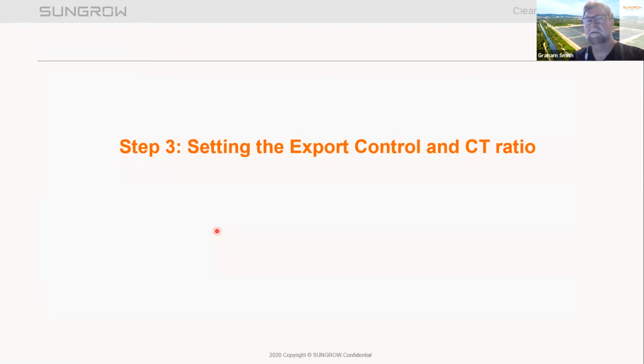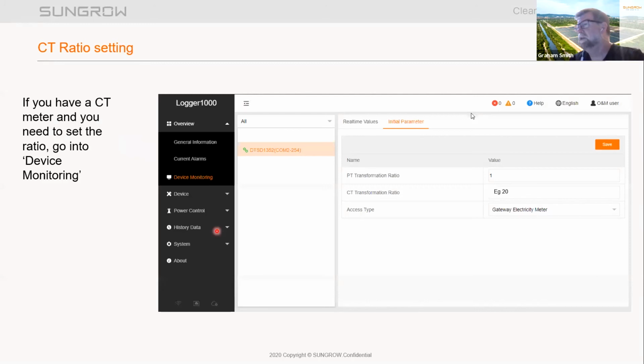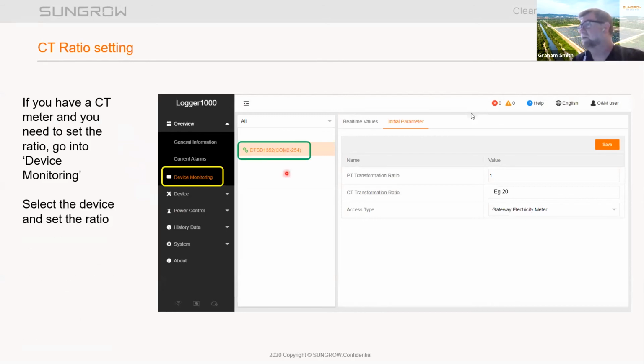Okay, so once you've done that, you've got all your devices scanned. All you need to do, if you need to set the export control, it's just a couple of little settings here, nice and easy. So you go into device monitoring here on the left hand side, and your meter will come up on the list of devices connected, so you just select the meter, and you select initial parameter, and down here is your CT transformer ratio. So obviously if it's a 100 amp supply, you're going to use 100 amp CTs, which is 100 divided by 5 is 20, and you just put your ratio into there and then hit the save button, and that's done.